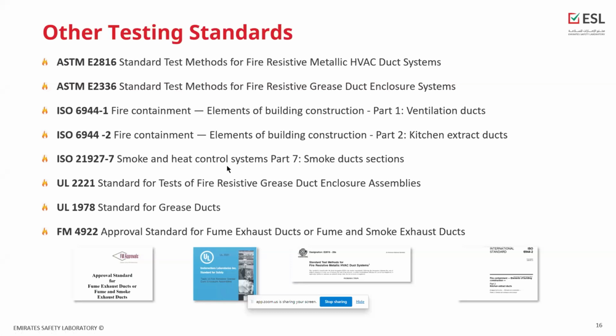And we can note here also that for kitchen extract, since this application is crucial, as explained, there is a specific standard which is targeting only the grease duct or the kitchen extract ducts. We also have the UL standard as well as the FM standard, but FM is a different concept. It does not come under the same category as the smoke control ducts, but they have a different categorization for the ductwork.